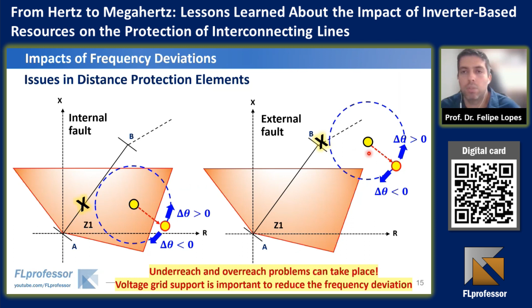Another aspect that I have seen and that has been widely commented in the literature regards the doubly fed induction generator units, and it is related to the crowbar operation. We know that in fault cases, there are some high currents that may flow through the rotor, and thus this rotor connection here through the converter may establish high currents through the switch, which is not good. Thus, the crowbar has the function to short circuit such a converter in such a way that when the crowbar operates, the doubly-fed induction generator becomes a simple induction generator.